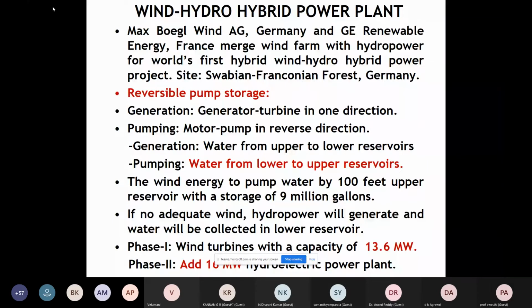So for wind hydro, they are going for this. Now what type of hydro power plant is there? It is equipped with reversible pump turbines. In one direction of rotation, they act as generator and turbine as in conventional systems, generating electrical power. But in the reverse direction, it is pumping. So in addition to the upper reservoir or dam, there is a lower reservoir also, and from the lower reservoir it is pumping water to the upper reservoir. This is the job of the reversible pump generator, and when there is a requirement, it starts generating. So the same set of machine which operates as generator and turbine, in the reverse direction starts operating as motor and pump.